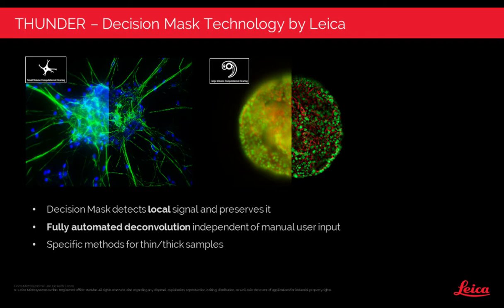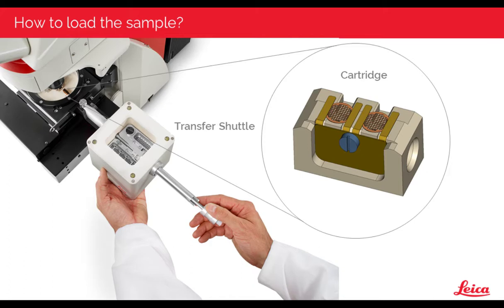Is it possible to use the microscope at room temperature, or is it only usable at cryo temperatures? You can use the system under room temperature conditions as long as you use grids. You can load the little cartridges with grids. The system cannot accommodate normal slides without removing the cryo stage from the top of the motorized stage. Normally, you would just use grids on the system.